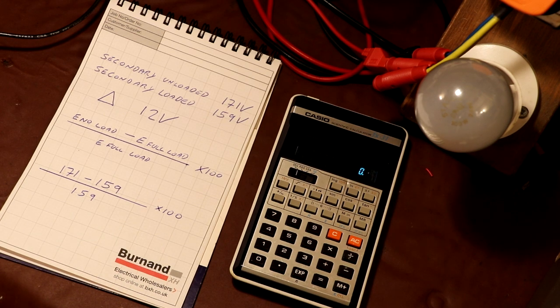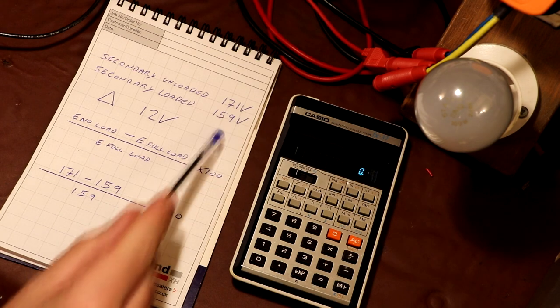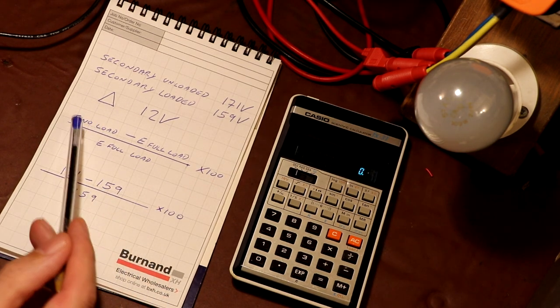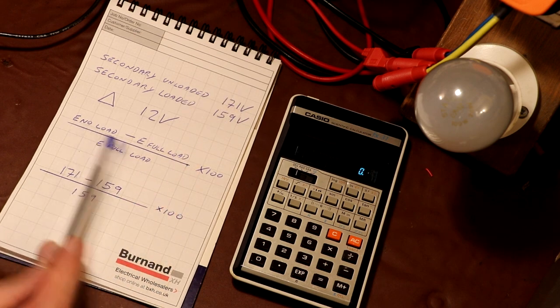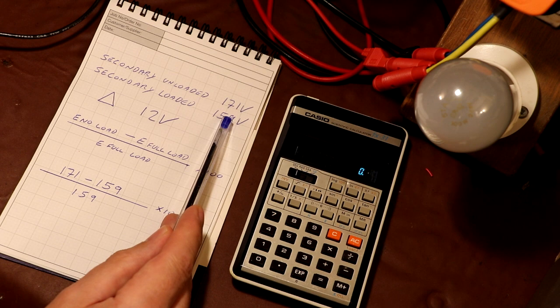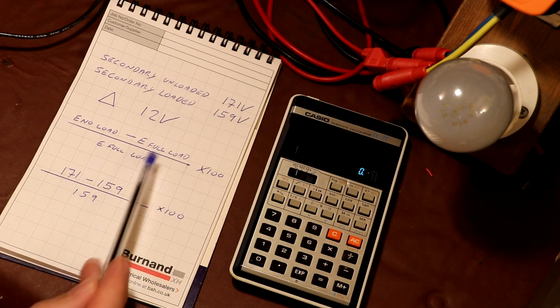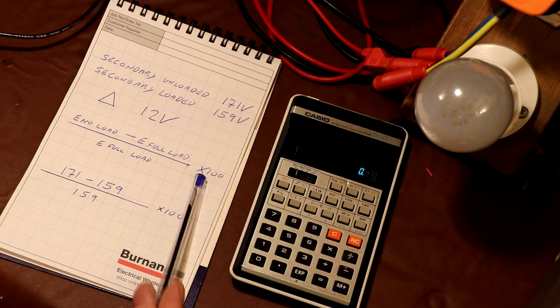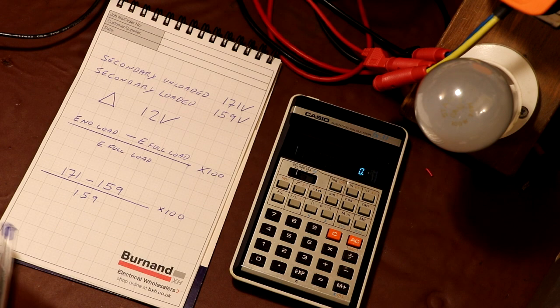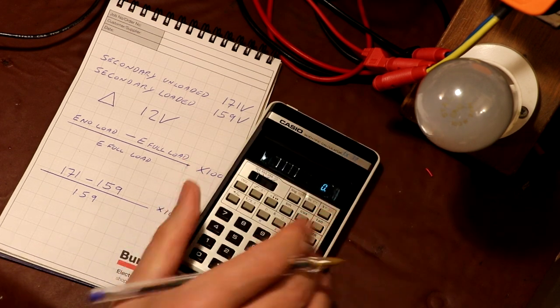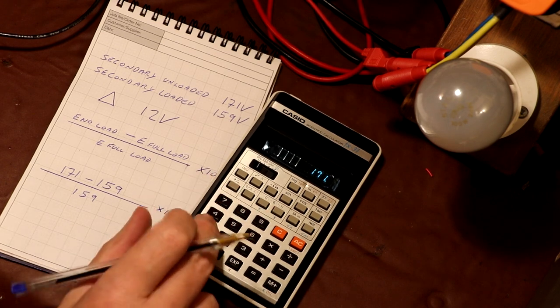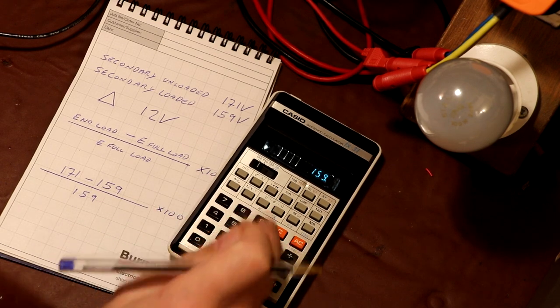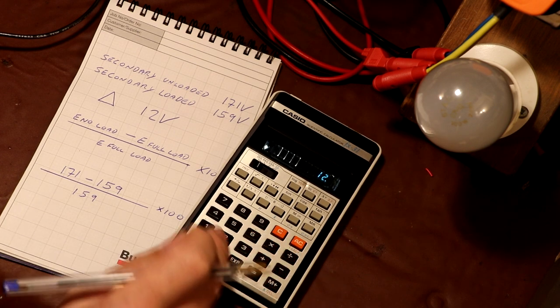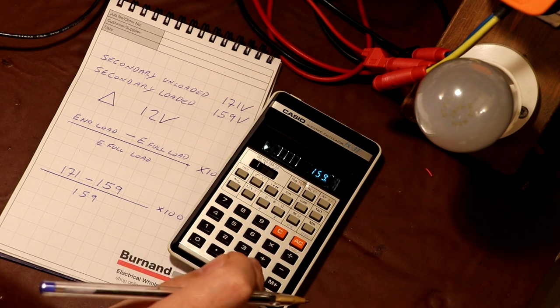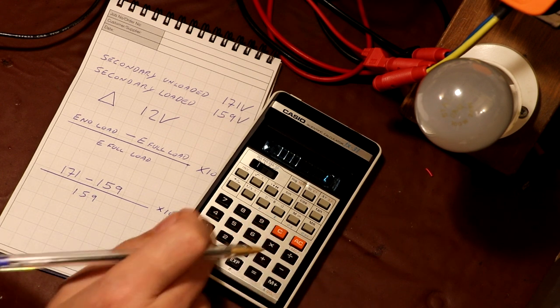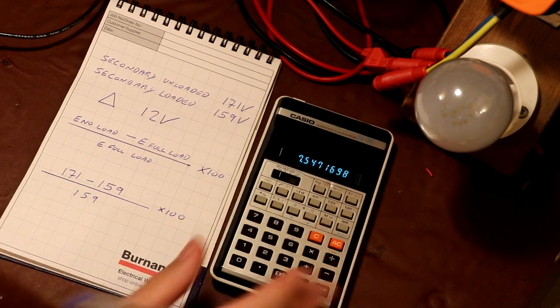So to work out the percentage voltage regulation of our transformer, we've got to take these numbers and put them into a formula. We need to take the no load voltage, which is 171, take away the full load voltage, 159, and then divide that figure by the full load voltage, 159 again, and then multiply that by 100, and we should get our percentage regulation figure. So let's go ahead and do that. 171 minus 159 is 12, and then we divide that by 159 and multiply by 100. So we're going to have 7.54%, write that down.